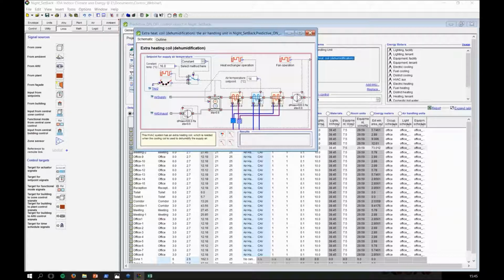Yeah. But I think you should also know it's possible to build anything really around the air handling unit, measuring the humidity, whether you want to control the flow rate or the humidity in the supply air or in the return air. On the screen you can see, for example, a default air handling unit called extra heating coil dehumidification. You start with a simple air handling unit, and then you can build a control around that cooling coil where you dehumidify the supply air, based maybe on the return air. So that's available. But we have done some swimming halls, and we end up in quite sophisticated simulation models with heat pumps, also taking energy from the wastewater and so on. We can always help you on a consultancy basis if needed.